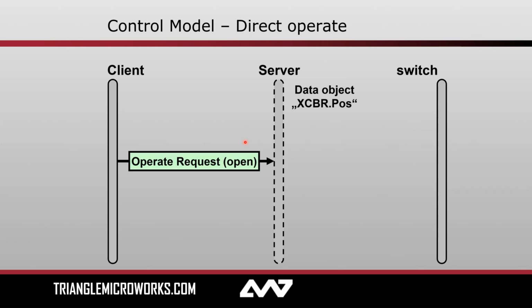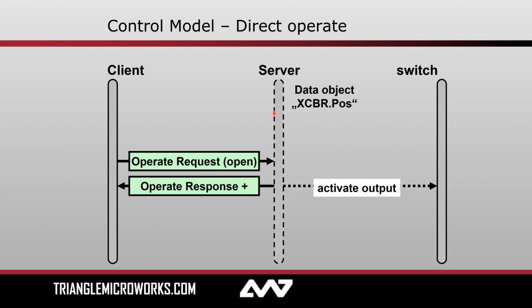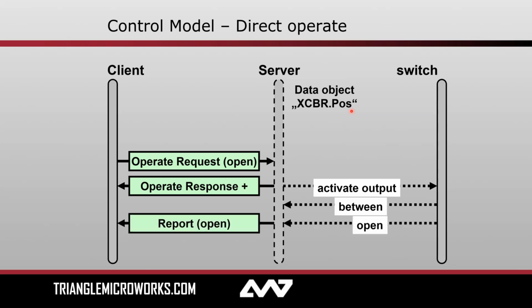Starts out with an operate request initiated from the client. So from a practical standpoint, this is you clicking a button from a control center, and the rest of this is just what's happening under the hood. So the server will receive this request to try and open the breaker. It will send back a response. Crucially, and this is a difference that we'll go into a moment here with, quote, normal security, it's just a response saying, "I have received your request and you're allowed to do it." And it will try and activate that output. In this case, it's an XCBR position, so we're actually trying to open a breaker. There'll be a momentary in-between state where the breaker is changing, and then eventually it will have opened and the action will be completed, and a report will be sent back to the client, letting it know, "I'm finished trying to do your requested control." Again, with normal security, there's not actually any confirmation here that we actually opened, but I'll talk about that in a moment.